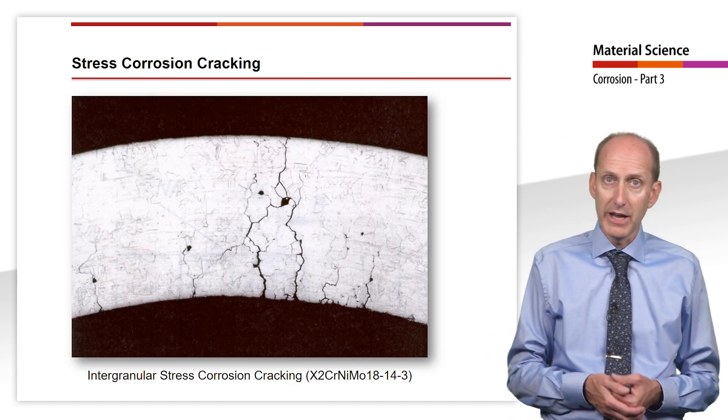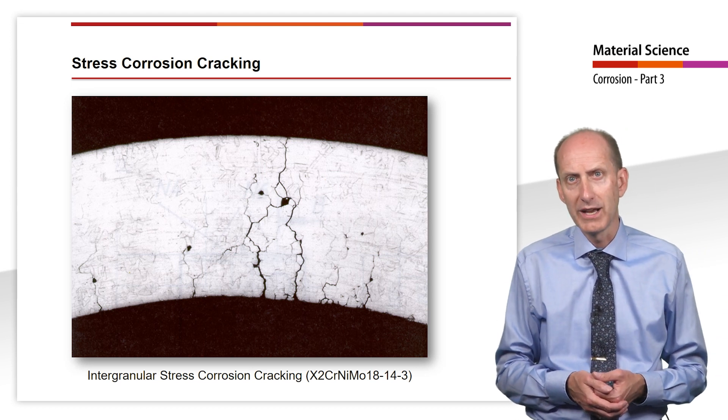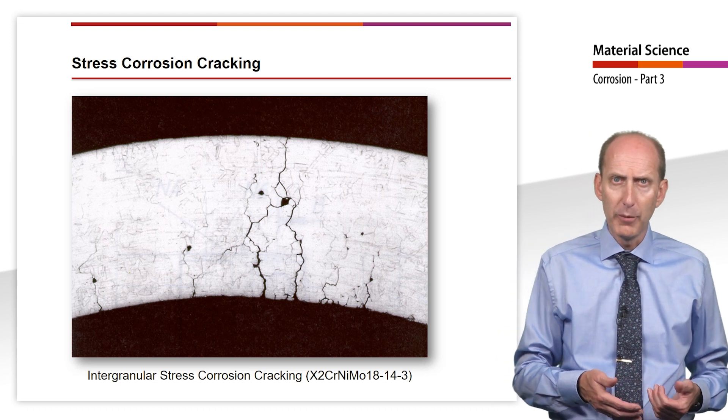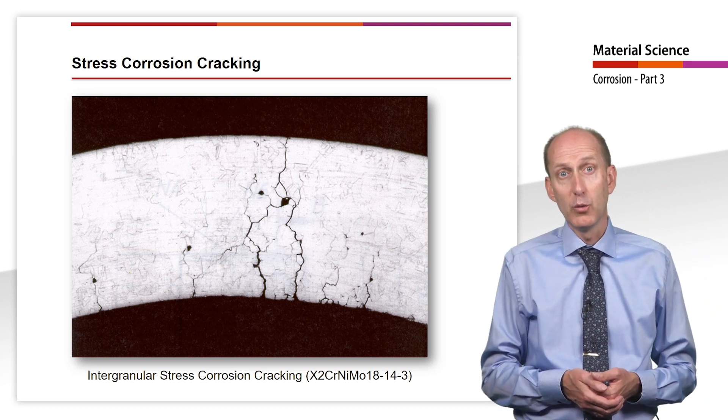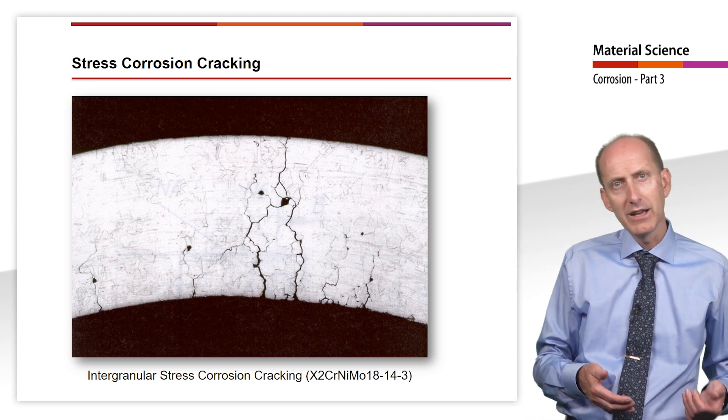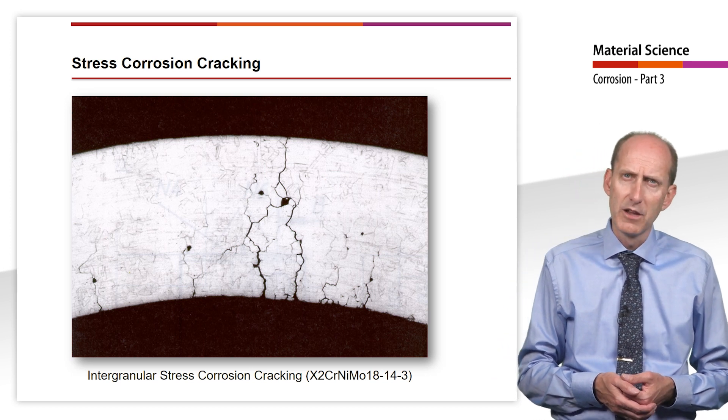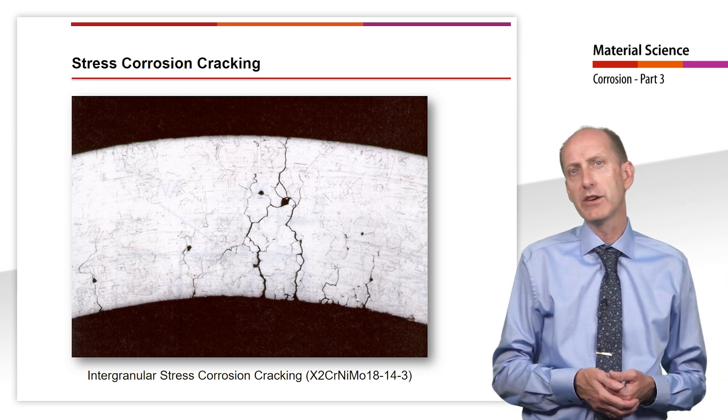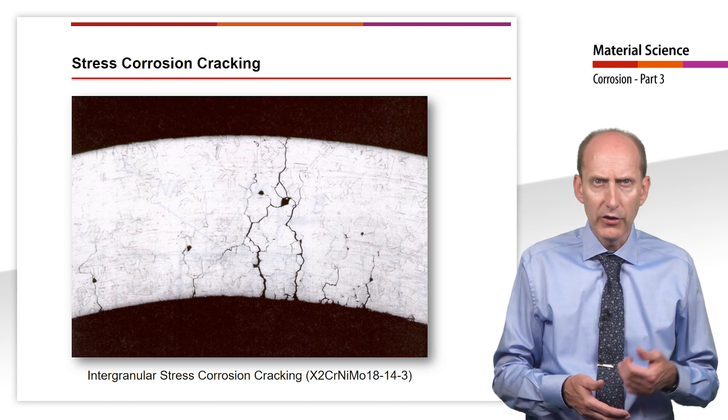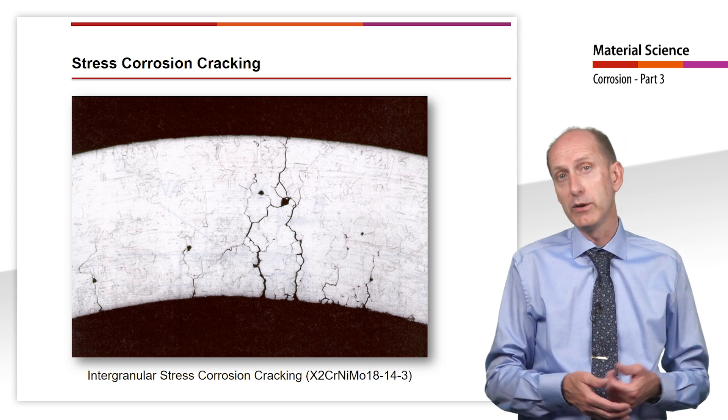This photograph shows a partial section of a tube from a shell and tube heat exchanger. The tubes were formed by cold working, which introduced such severe stresses into the material that intergranular corrosion occurred in the heat exchanger.